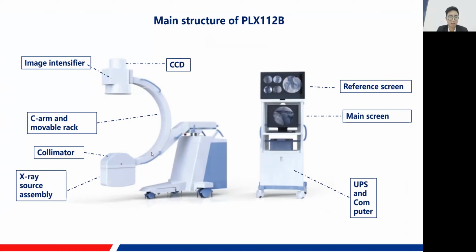The rack connecting the image intensifier and the X-ray source assembly is this movable rack, the C-arm movable rack, here, this one, C-arm. And of course we've got a workstation trolley, consisting of two screens, the main screen in the middle, and the reference screen on top.